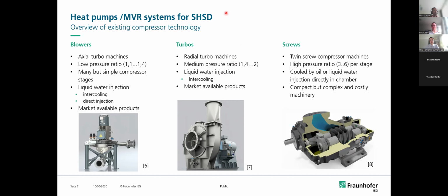Last but not least is the twin screw compressor machine. Here we could generally achieve the highest pressure ratios, 3 to 6, feasible, and they are sometimes cooled by oil, which wouldn't be suitable for this open loop structure. But here we could also use water.